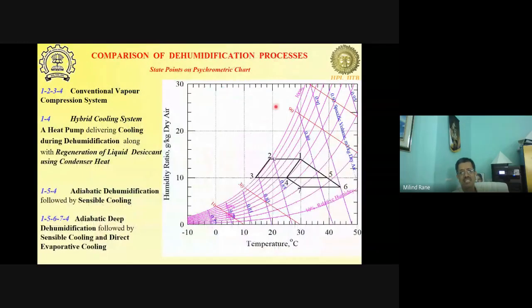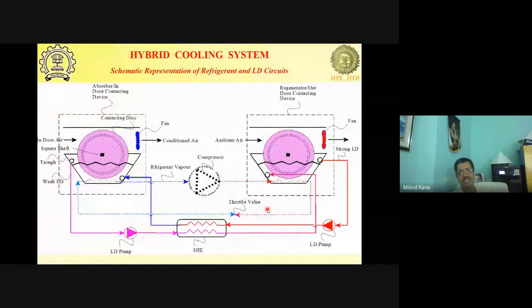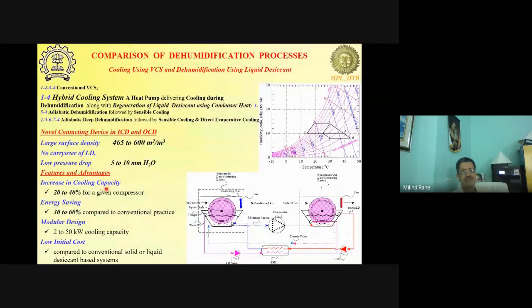Liquid desiccant hybrids. We can go from 1 to 4 in a single step using a hybrid air conditioning system. The advantage here is that the minimum temperature on the air side is only 24 here. So your evaporator need not be operating at 7.2. It can operate even at 18 degrees if the compressor can handle that. Okay. So that will increase the evaporator temperature, evaporator pressure will increase, evaporator pressure will increase the evaporator vapor density, increased evaporator vapor density will increase your mass flow rate through the compressor, and mass flow rate increase through the compressor can then increase your cooling capacity. So the cooling capacity for a given compressor can go up by 20 to 40%. Energy saving because of reduced pressure ratio can be 30 to 60%.